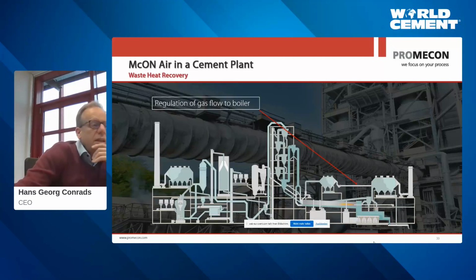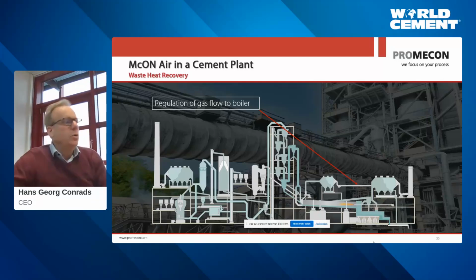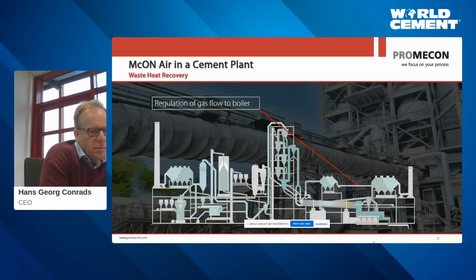Recently quite a few projects came along that dealt with waste heat recovery. Waste heat recovery is becoming bigger and bigger. More and more countries demand the use of the waste heat, and we have several OEMs that are building waste heat recovery systems for cement plants, which are inquiring our meters regularly. Because if you have a waste heat recovery boiler, you want to know the gas enthalpy going through the boiler on one hand, and you would like to know the water enthalpy going on the other end. And this will allow you to establish a measure for the cleanliness of the boiler, to see how effective the boiler is working.